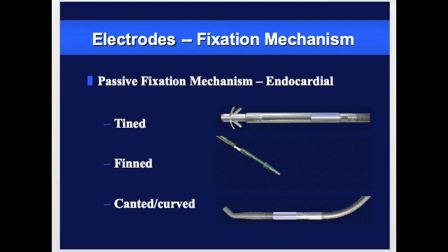Passive anchoring devices such as flanges, wedge tip cages and balloons were early attempts to solve the dislodgement problem of early pacing. However, only after tined leads were introduced by Medtronic in 1976 did a true solution to dislodgement emerge with regard to passive fixation. Today, there is approximately a 1 to 2 percent dislodgement rate with passive fixation leads, 1 to 2 percent in the atria and 1 to 2 percent in the ventricle.